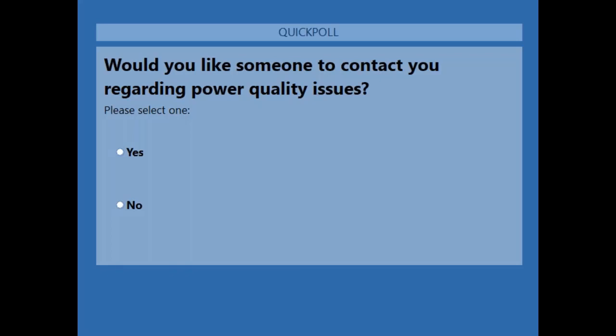We are dealing with a customer right now who is saving his client probably around $1 million because our equalizer system can do some power factor correction. There are a lot of guidelines in the power purchase agreement between a solar generator and Georgia Power or the Southern Company, and usually they require that you be able to provide full load between 0.95 lagging and 0.95 leading power factor. If you can't, then they reserve the right to modify your power purchase agreement, of course, downward.